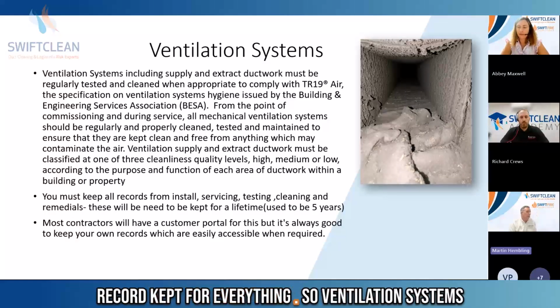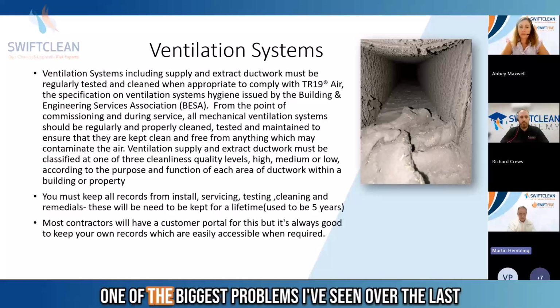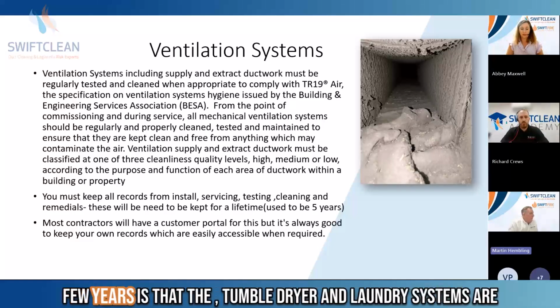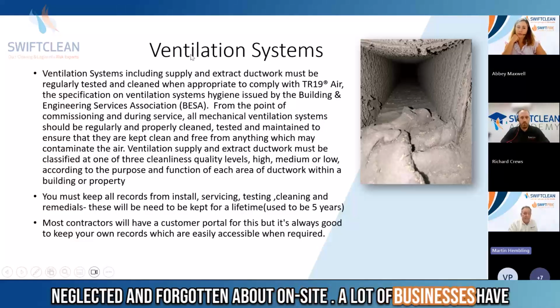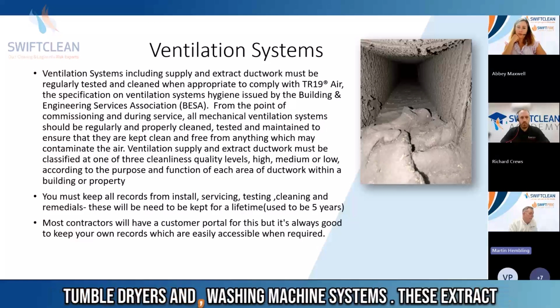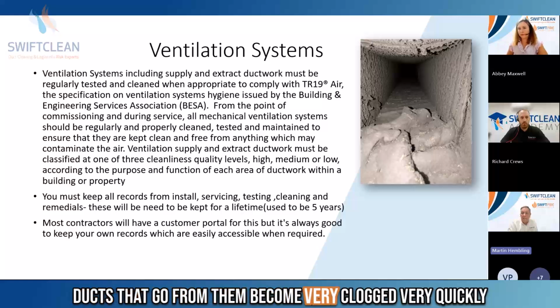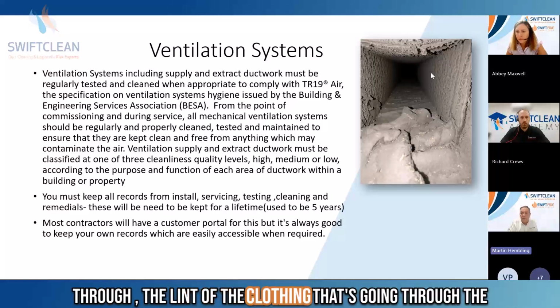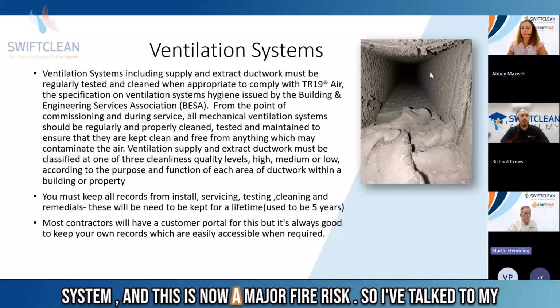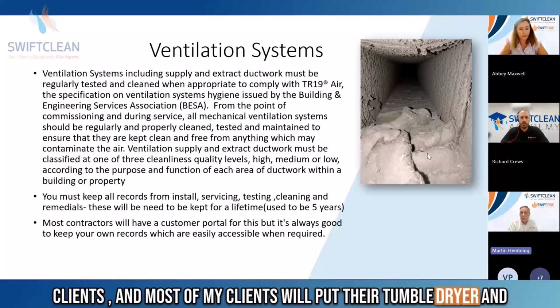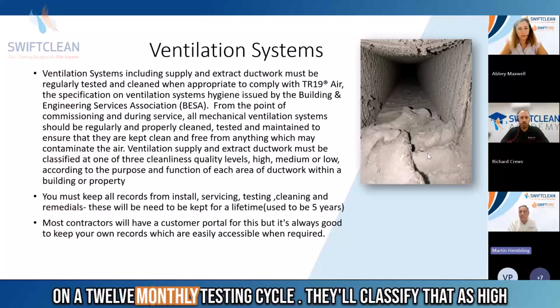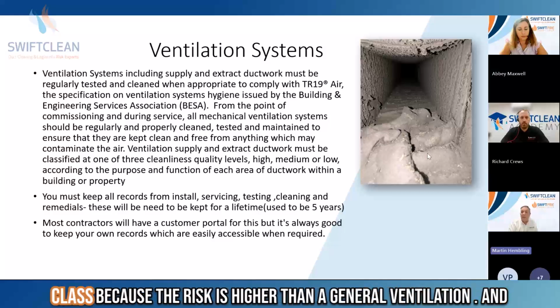So ventilation systems, one of the biggest problems I've seen over the last few years is that the tumble dryer and laundry systems are neglected and forgotten about on site. A lot of businesses have tumble dryers and washing machine systems. These extract ducts that go from them become very clogged very quickly through the lint of the clothing that's going through the system. And this is now a major fire risk. So I've talked to my clients, and most of my clients will put their tumble dryer and laundry extracts on a 12 monthly testing cycle. They'll classify that as high class because the risk is higher than a general ventilation.